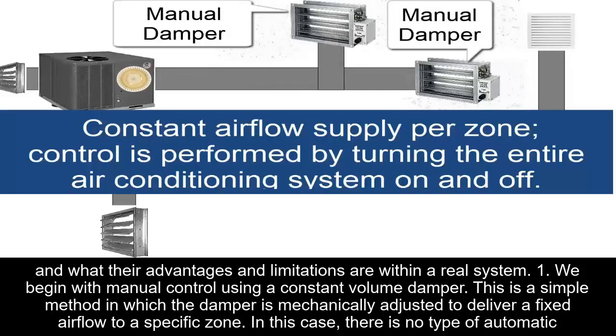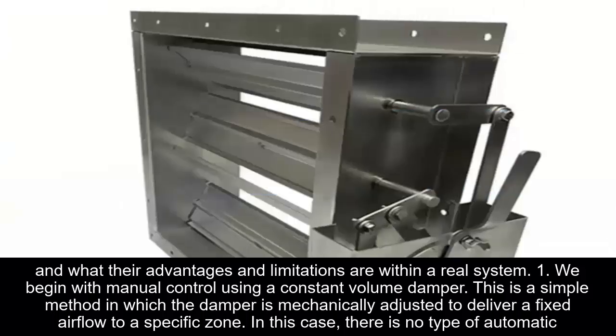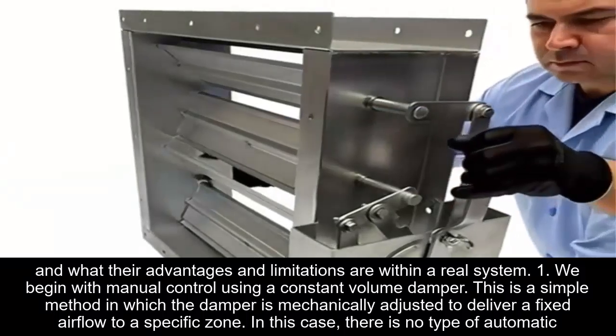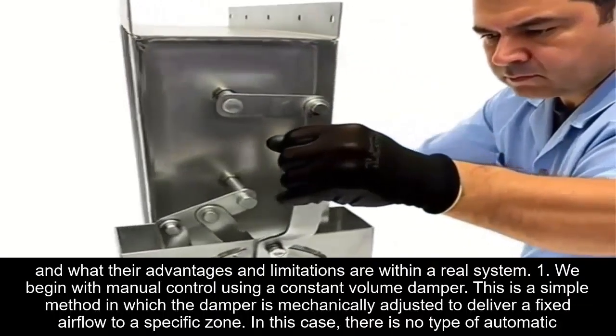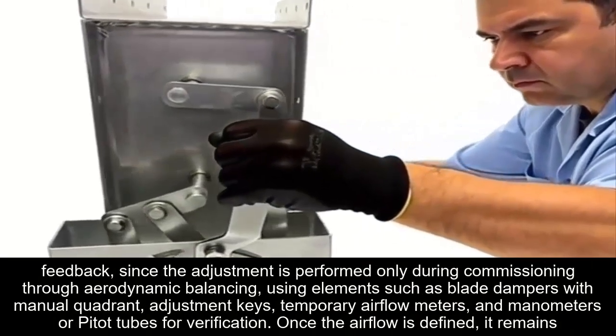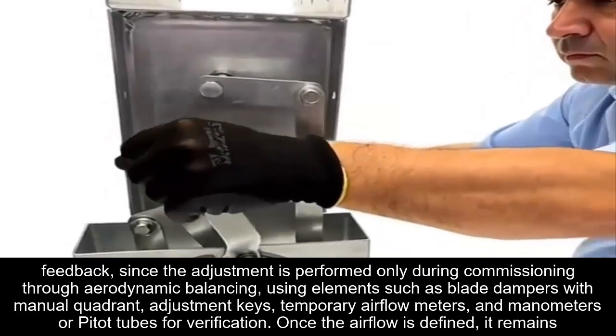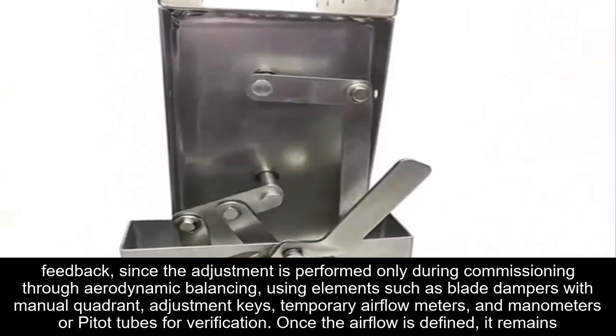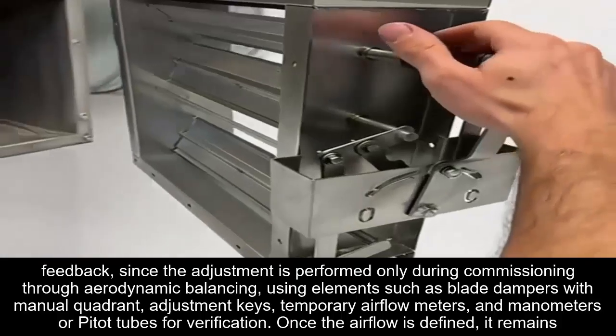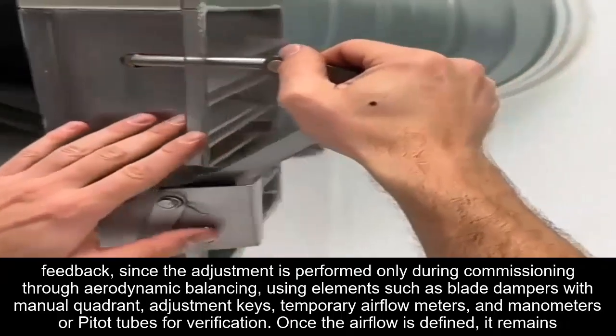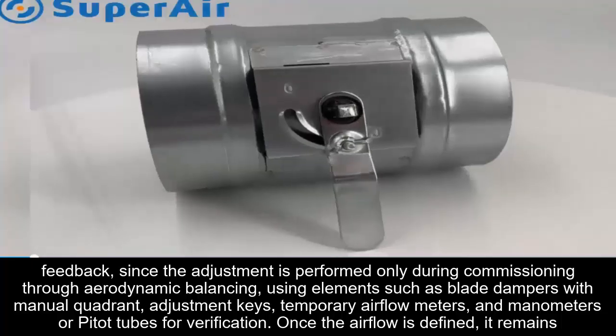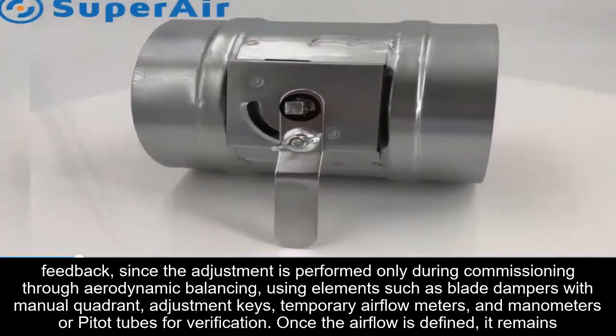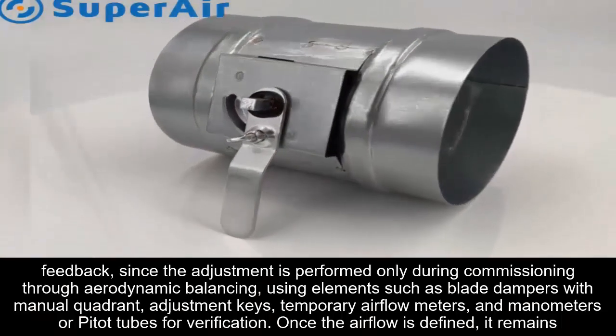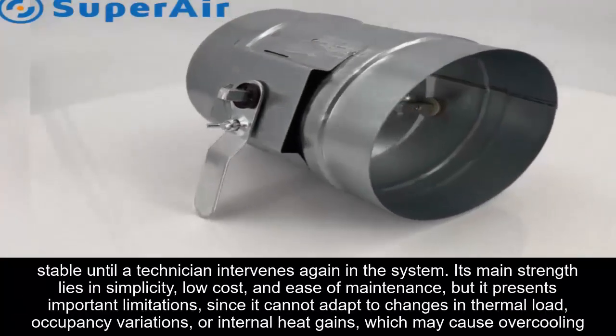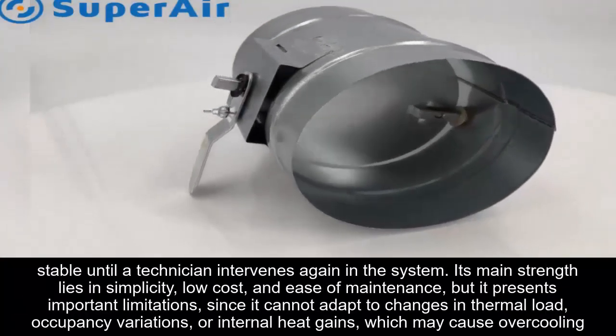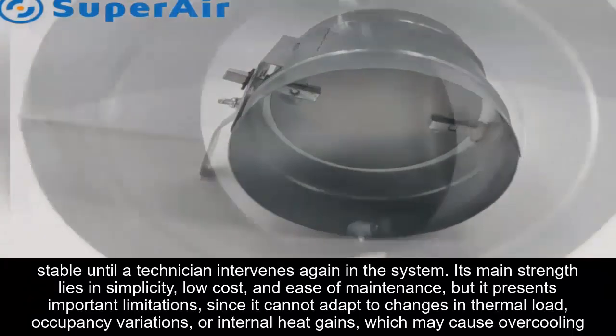This is a simple method in which the damper is mechanically adjusted to deliver a fixed airflow to a specific zone. In this case, there is no type of automatic feedback, since the adjustment is performed only during commissioning through aerodynamic balancing, using elements such as blade dampers with manual quadrant, adjustment keys, temporary airflow meters, and manometers or Pitot tubes for verification. Once the airflow is defined, it remains stable until a technician intervenes again in the system.